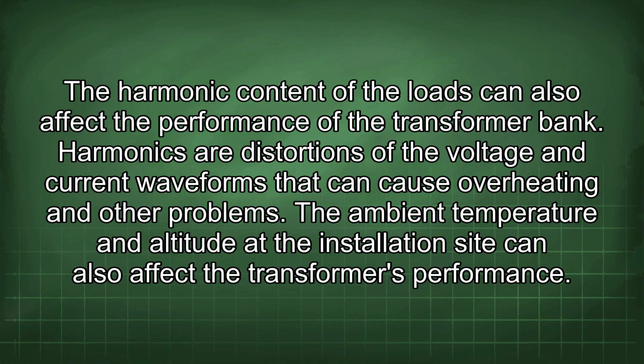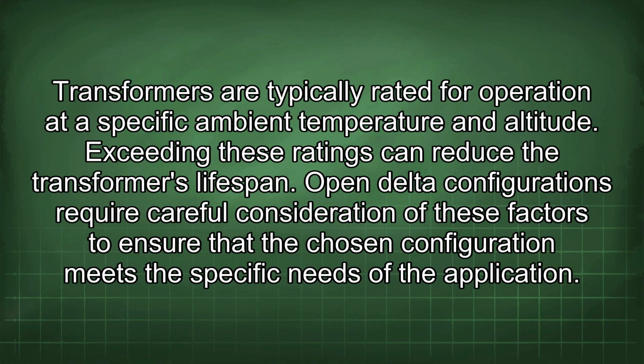The ambient temperature and altitude at the installation site can also affect the transformer's performance. Transformers are typically rated for operation at a specific ambient temperature and altitude. Exceeding these ratings can reduce the transformer's lifespan.